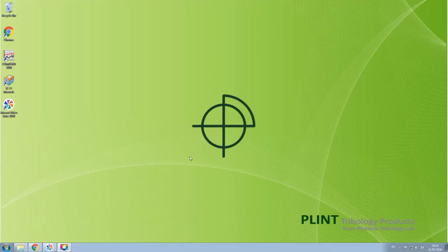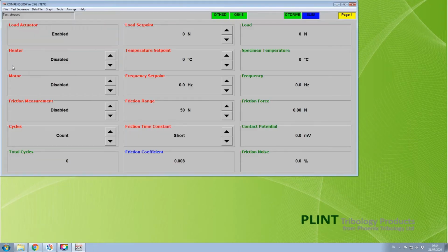Double-clicking the Compend icon on the Windows screen launches the software at page 1, the primary user interface screen. A single screen or page contains up to 40 boxes, and there are a total of 6 pages. Page 2 is for manual control of the high-speed data acquisition channels. Pages 3 and 4 are available for controlling additional peripheral devices if required, and for additional sensors and derived channels. Page 5 is used for calibration. Page 6 duplicates boxes from page 1 and is used to define the order of columns in data files. It may also contain machine status information that can be used for fault finding.